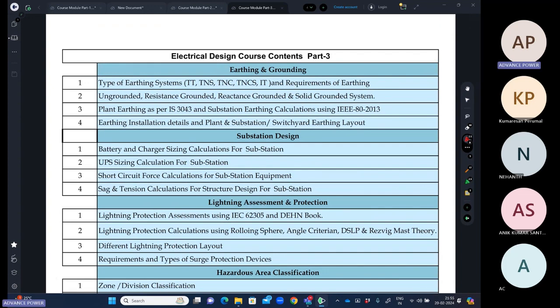The next part will be earthing and grounding. We'll discuss the basic concepts of the earthing system. You might have seen the TT type, TN-S, TN-C, TN-C-S, IT. These are based on the earthing provision at the substation end and the earthing provision at your premises end. Types of grounding are ungrounded, resistance grounded, reactance grounded, solid grounded. Based on this, these notations change. For which application we use which earthing system, why earthing is required, and the types of earthing systems, we'll discuss in very much detail.